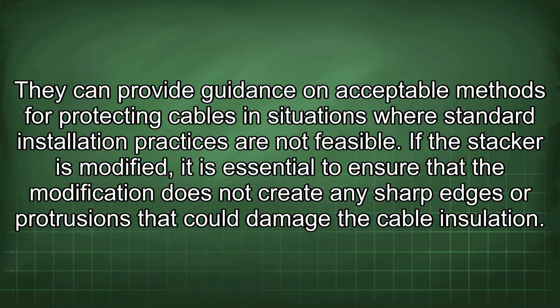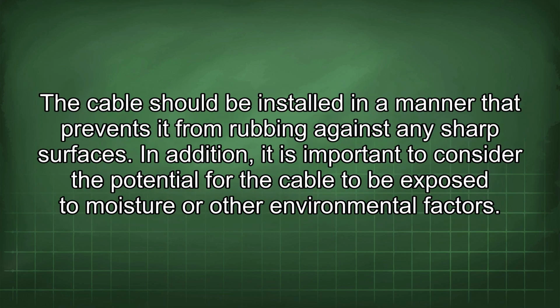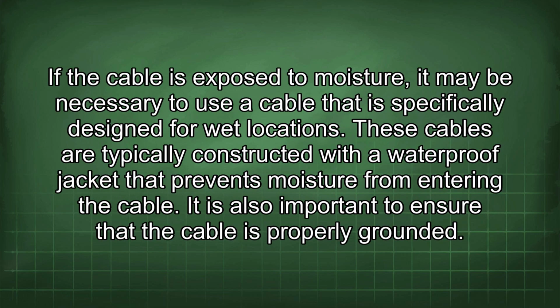If the stacker is modified, it is essential to ensure that the modification does not create any sharp edges or protrusions that could damage the cable insulation. The cable should be installed in a manner that prevents it from rubbing against any sharp surfaces. In addition, it is important to consider the potential for the cable to be exposed to moisture or other environmental factors. If the cable is exposed to moisture, it may be necessary to use a cable that is specifically designed for wet locations. These cables are typically constructed with a waterproof jacket that prevents moisture from entering the cable.